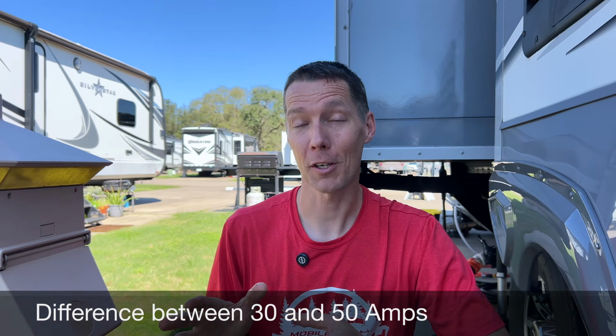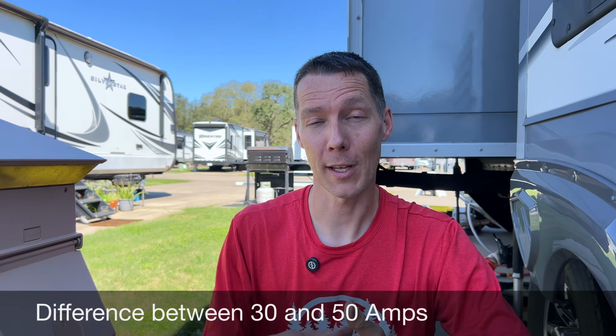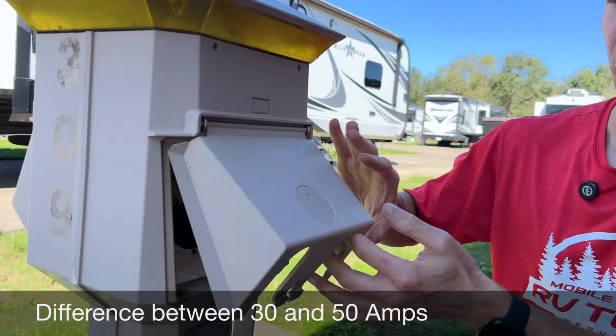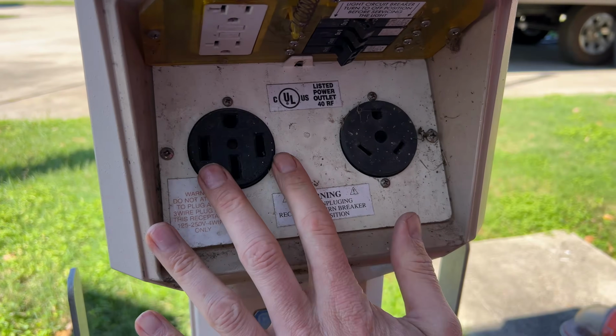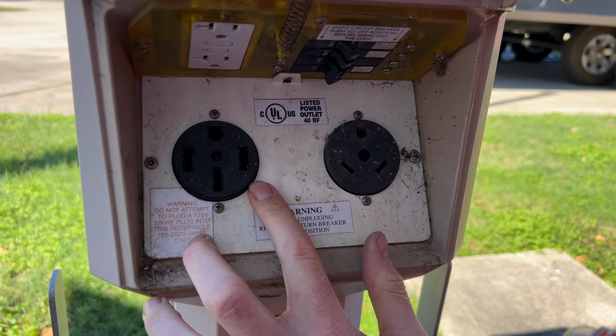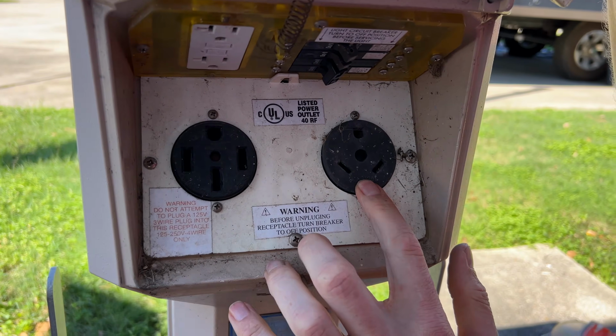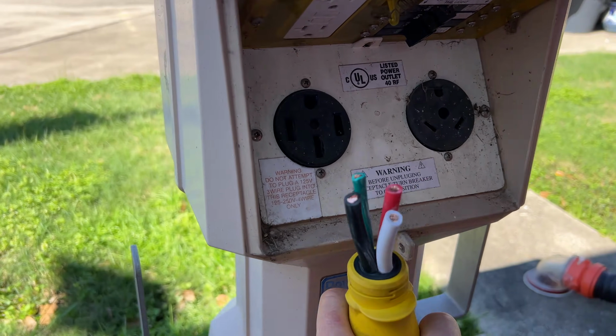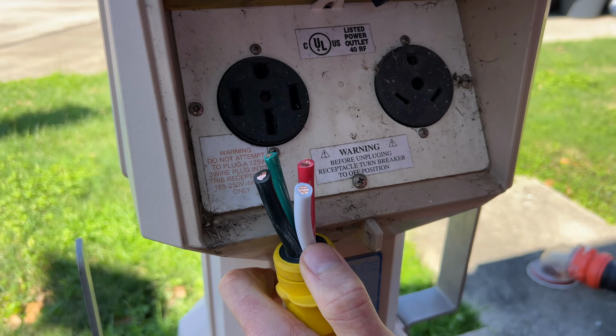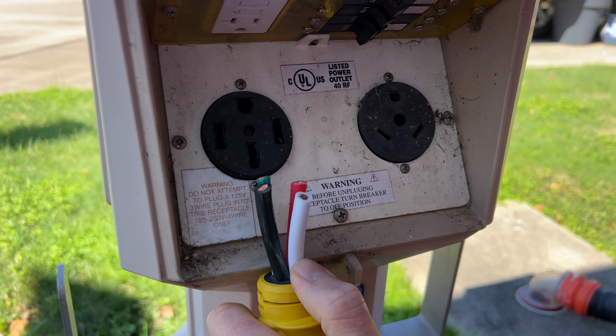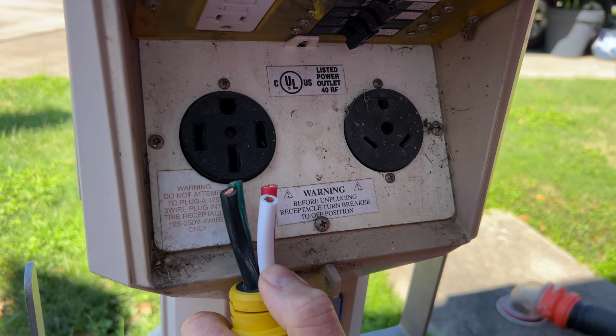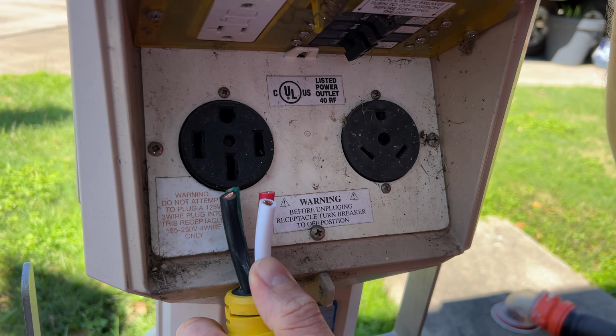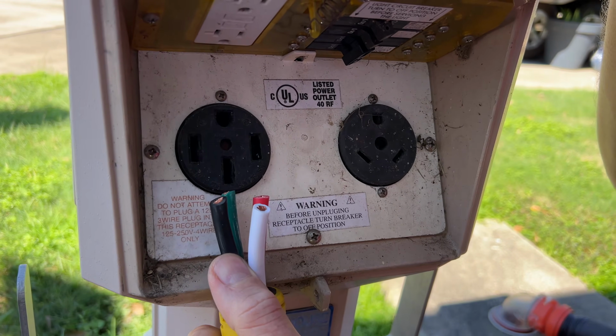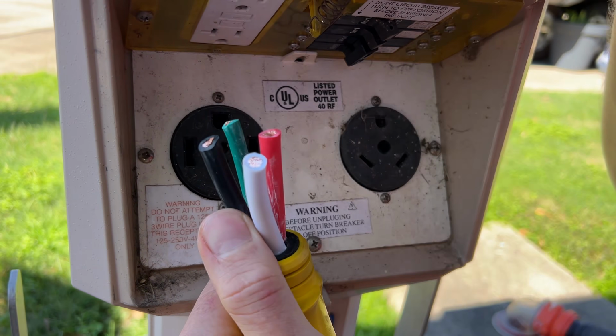Now, as I mentioned earlier, I'm going to cover the difference between 30 amp and 50 amp power. Looking at the pedestal, we have a 50 amp outlet with 4 prongs, and a 30 amp outlet has 3 prongs. Inside those 4 prongs, there's 2 hot legs, 1 ground, and 1 neutral. The combination of all that gives you 50 amps of power on each hot leg, for a total of 12,000 watts of power in the 50 amp RV.